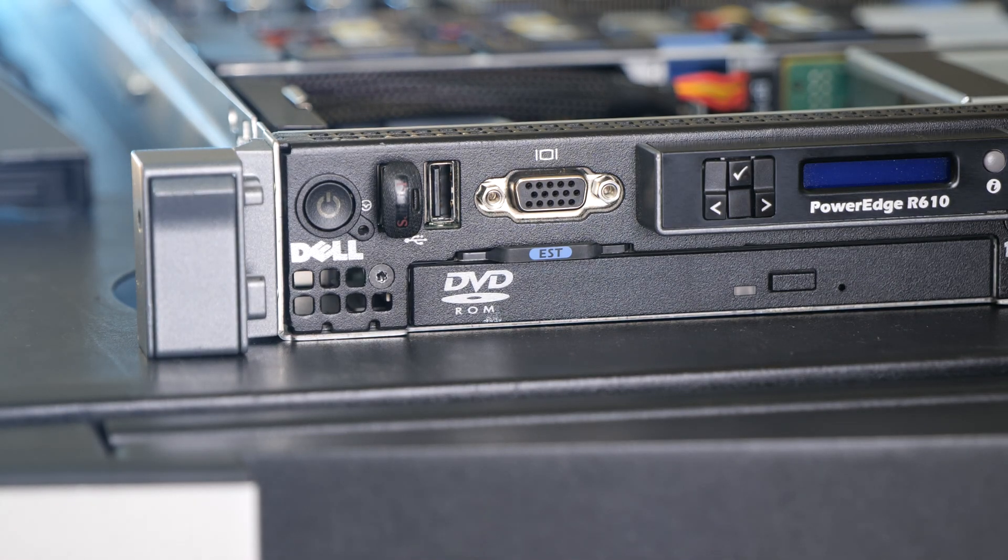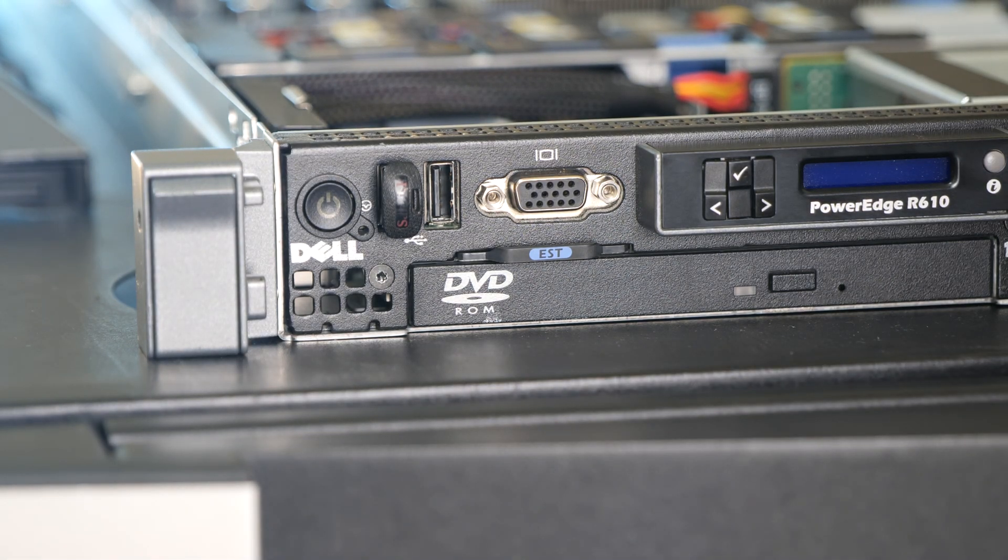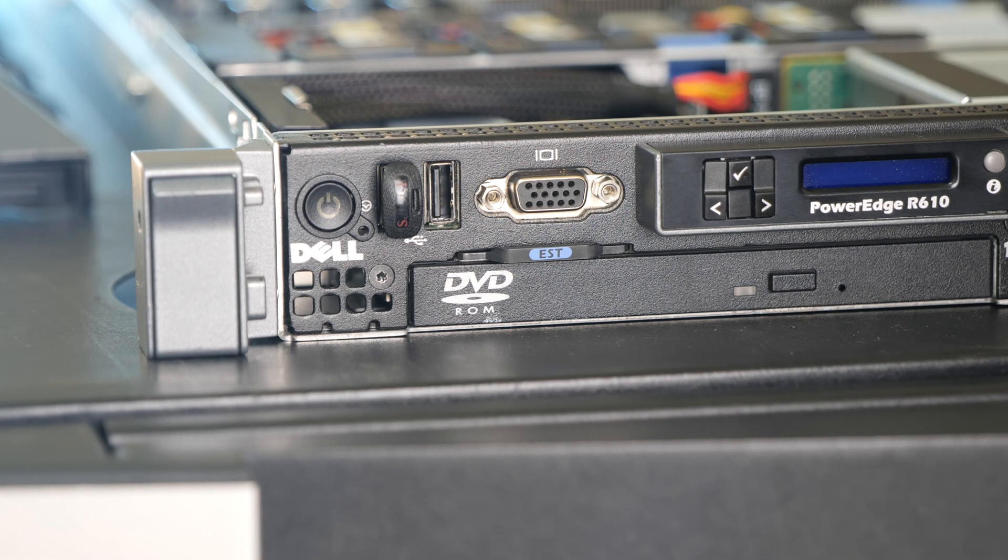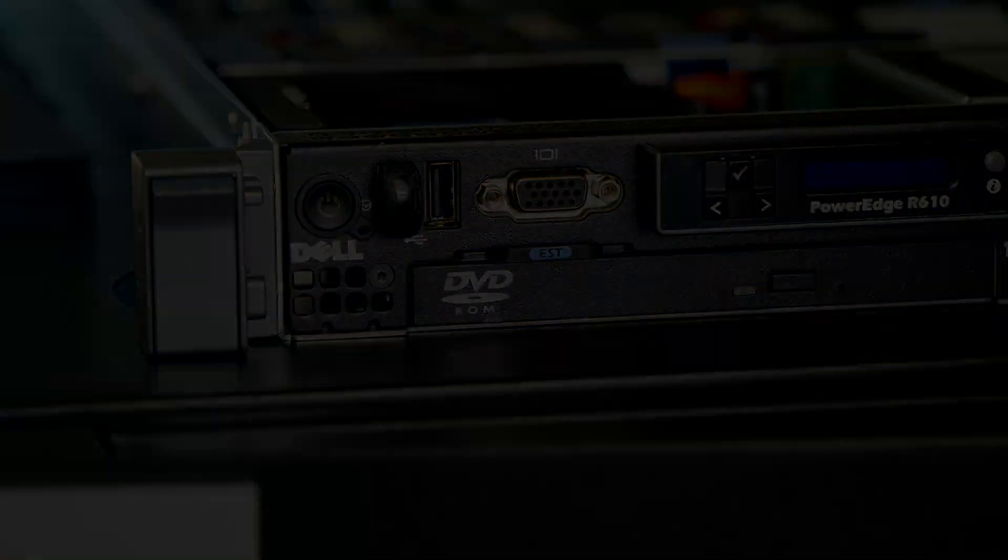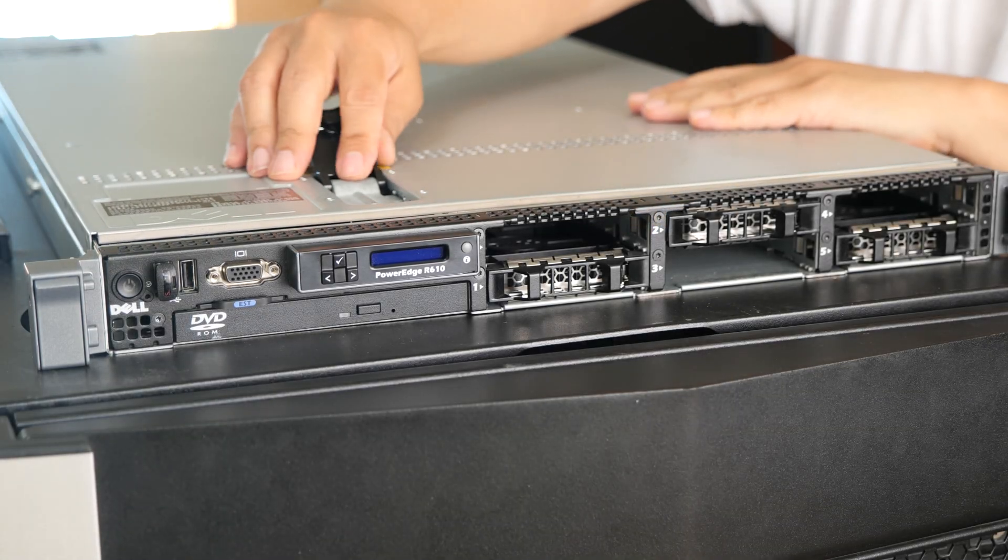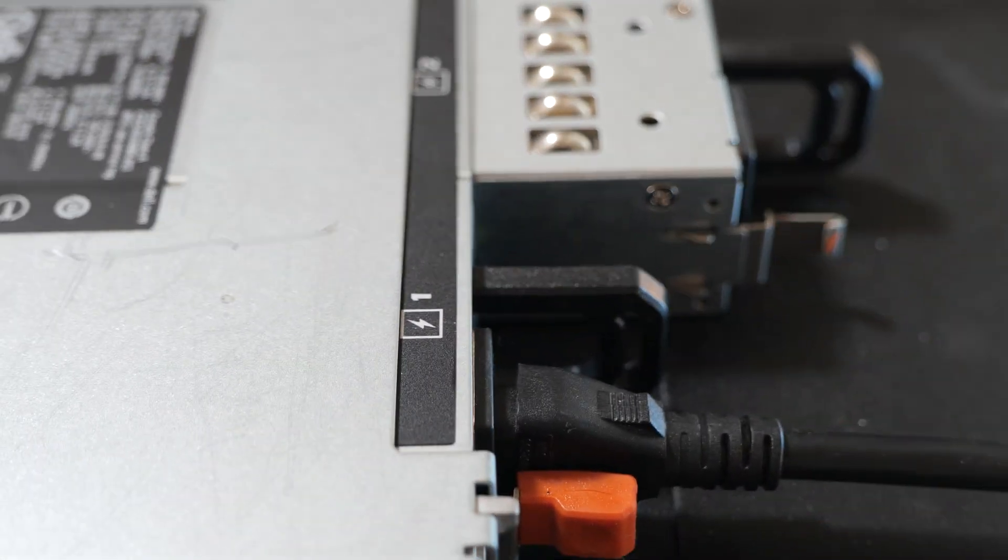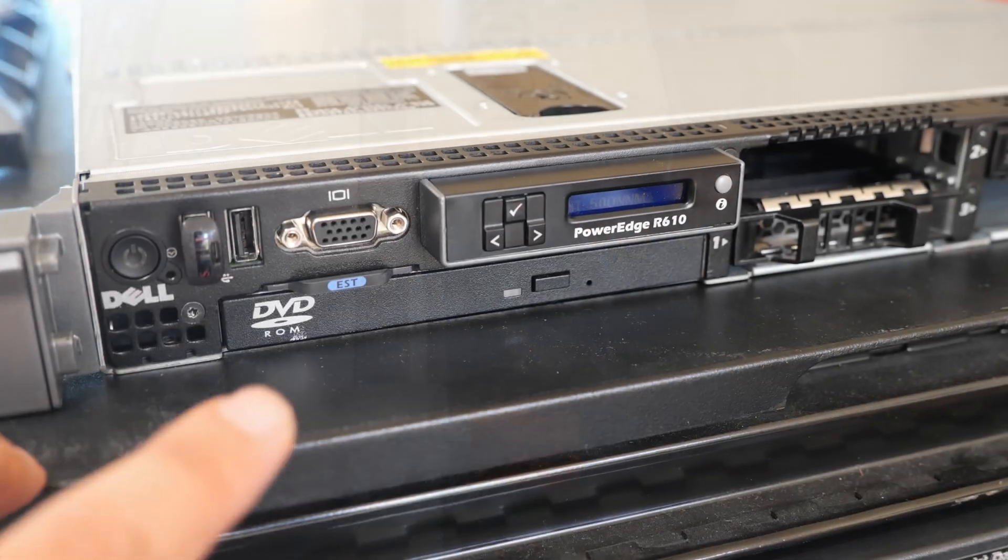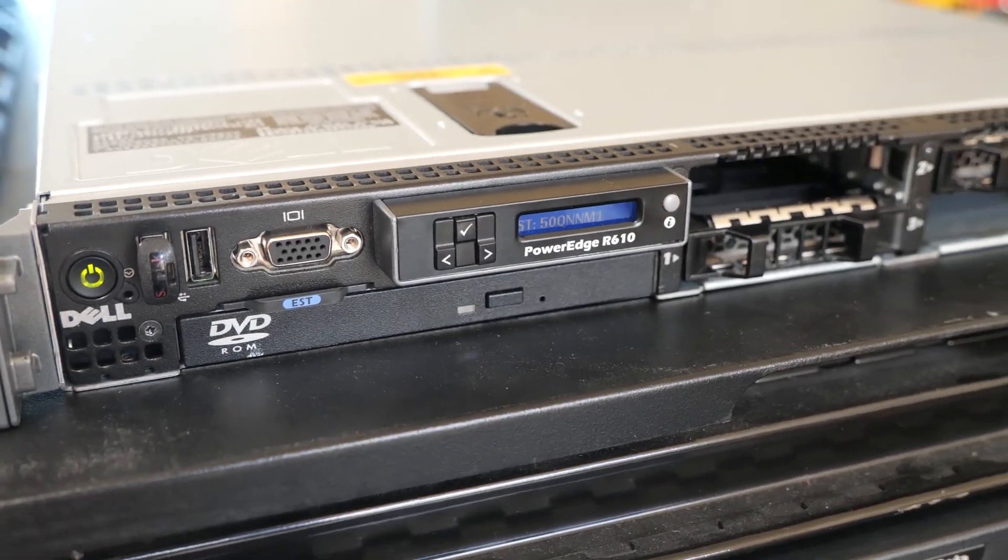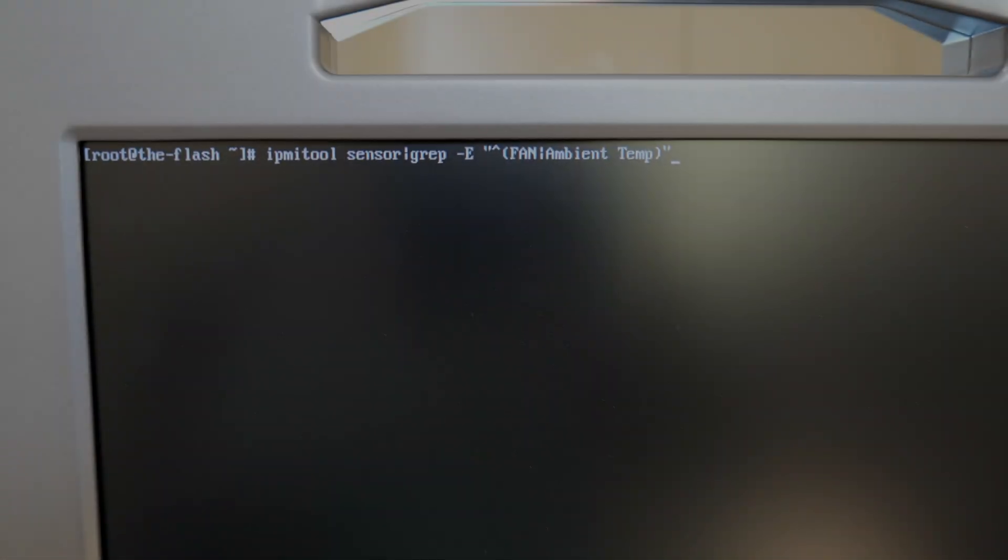All right, so that's it for getting the front I.O. panel controller board replaced that has that ambient temperature sensor. So let me plug my USB boot drive back in. So let's power this guy back on and see what the ambient temperature reads. And we should also notice, if it's reading correctly, we should notice that the fans are going to run a lot slower and quieter.